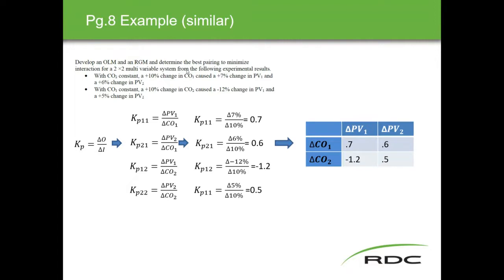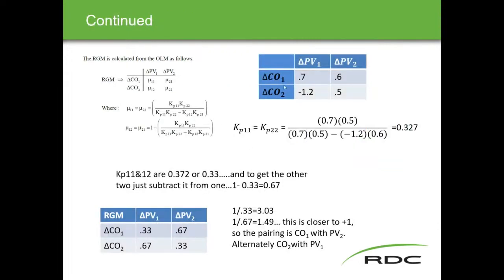Controller two is held constant. We do a 10% change in CO1, which caused a 7% change in PV1 and a 6% change in PV2. The 10% change is common to both tests. For controller one: output change 6 over 10 gives 0.6, and 7 over 10 gives 0.7. PV1 with controller one goes into position 1,1 and position 2,1 gets 0.6. The associated second half of the test generates numbers the same way to fill out the open loop matrix grid.